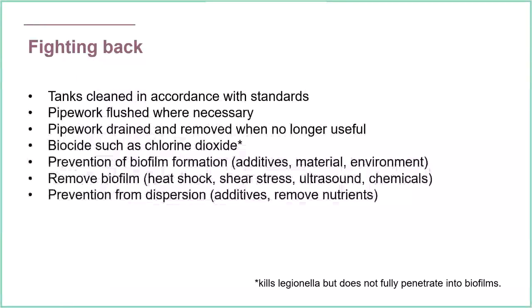A biocide such as chlorine dioxide - that's an additive which can be included into liquids, and that kills Legionella. However, part of the benefit of a biofilm, as far as the bacteria are concerned, is that it protects itself from those sorts of chemical attacks. So the chlorine dioxide will kill Legionella, but it won't necessarily eliminate the biofilms where it may be living.